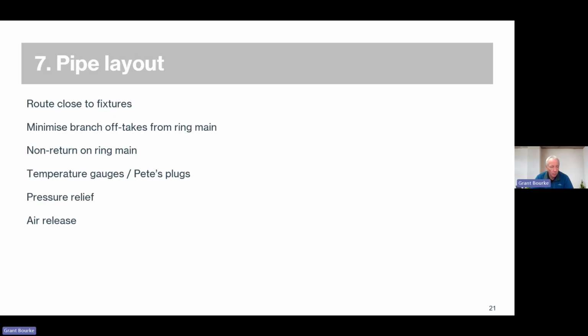Air release we didn't. Often in a small domestic system, you'll get away without automatic air release valves. It depends just how you're going to organise the piping. You may need some on a 2 or 3 story building, but have a bit of a think about how you're going to get the air out of the system. In the book, we've got a couple of little tips that can help you with that one. Don't always need it with a simple system on a single level, but you can get into trouble if the ring main pumps we use aren't terribly grunty. So just have a bit of a think about the air release.